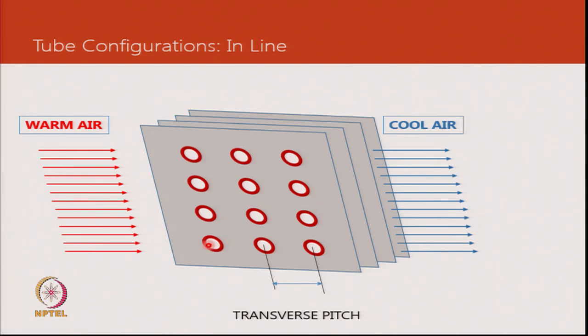In a simple in-line fin-on-tube construction, some tubes are in the shadow of earlier tubes, meaning some air flows through without full contact while refrigerant flows through all the tubes. The task is to find the optimum combination of diameter, fin thickness, and tube placement — distance between tubes — to achieve optimum value for the investment in a heat exchanger.